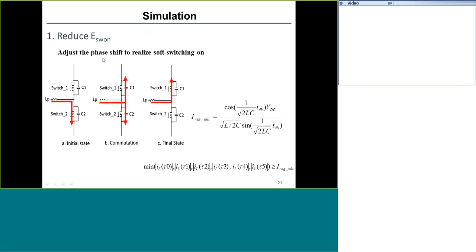Now, furthermore, if we want to reduce the turn-on loss to realize ZVS, we have to guarantee the current in the leakage inductor of the transformer is large enough during the deadband to deplete the energy stored in one of the switch junction capacitances. I won't talk too much about where this equation comes from, but the minimum current we have to secure for the devices is a function of deadband selection, junction capacitance, and leakage inductance.